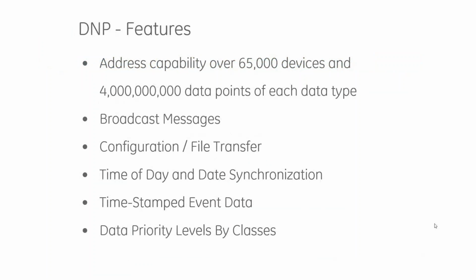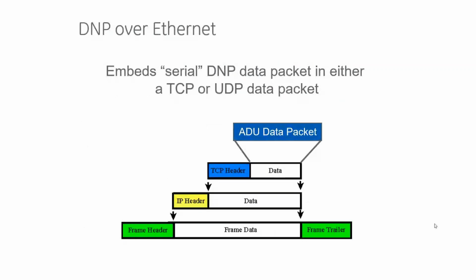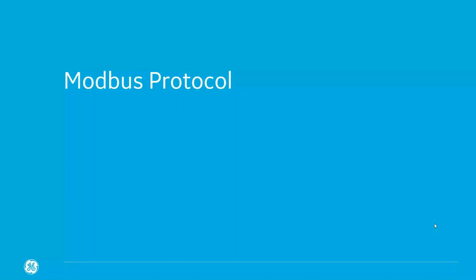talk about standard interoperable protocols, and DNP is one of those protocols where if two devices are talking together, there's no proprietary way of sharing that information. It's a standard, so multiple vendors can support the same protocol. Some of the features, I talked about a lot of these, but just want to mention that basically what DNP over Ethernet is, is how do we packet the serial data into an Ethernet packet, and that's what it defines. Taking that serial data, putting it in an Ethernet packet, and transmitting it over an Ethernet network.